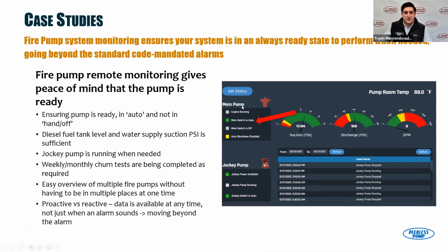So getting an overview that, for example, your pump is on, that it's in auto and it's not turned off. And this is especially important if you've got a global portfolio of fire pumps. If you're a multinational and you're responsible for life safety throughout all your facilities, just making sure that your pumps are ready to go when you need them to. Critical data, like making sure you've got adequate suction pressure so that pump, if it needs to turn on, will be fed accordingly. That your jockey pump, because that is the pump that runs day in and day out, is running, and that it's got power available, and then it's set to run.